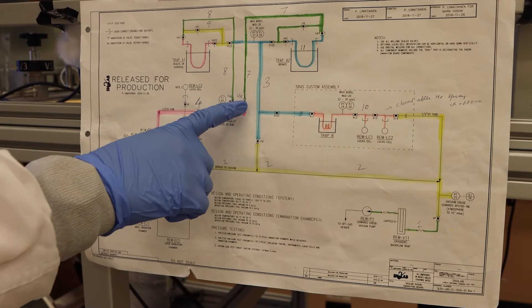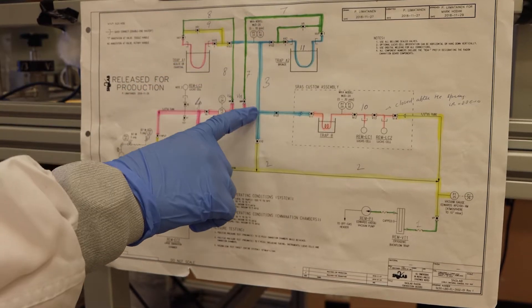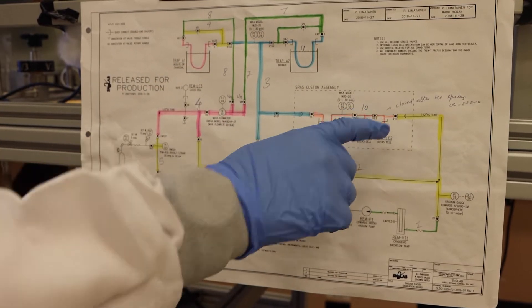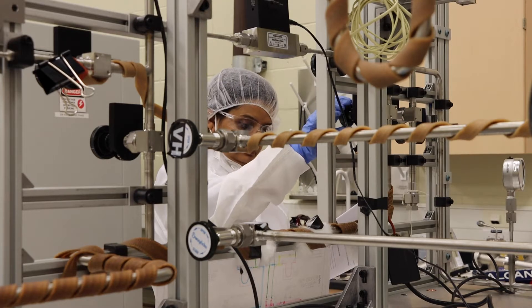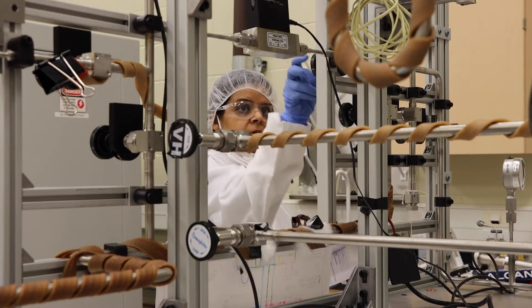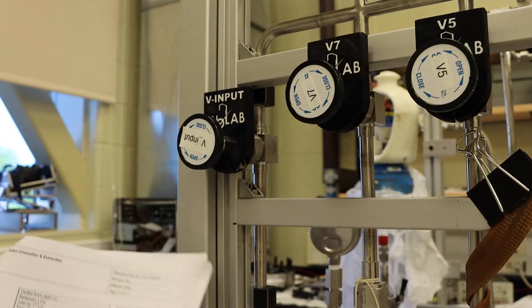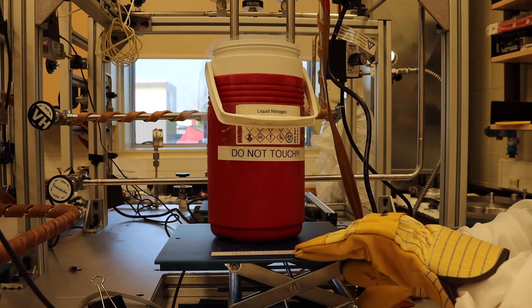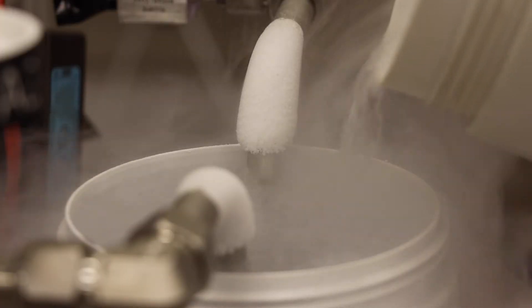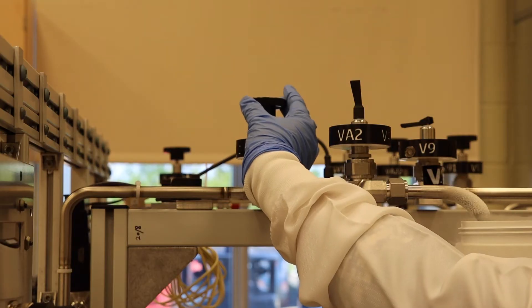Afterward, the extraction phase begins, where radon will travel through an emanation board designed to isolate it. The scientist prepares the correct valve configuration to allow the radon to move from the emanation chamber to the primary trap. Next, the scientist immerses the primary trap in liquid nitrogen, which brings the trap to the exact temperature where radon will stick to it. Other gases will remain in the gas phase and be pumped out of the system.